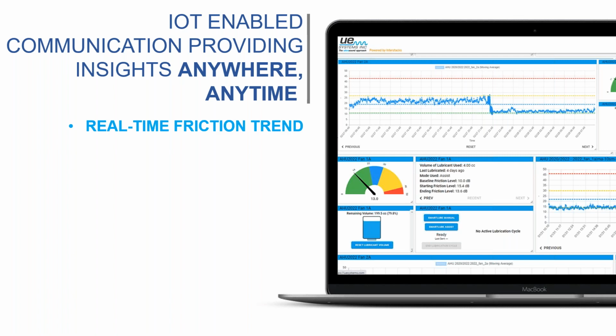So we have a real-time friction trend. Hopefully you can see my mouse. If you can't, that blue squiggly line is that friction trend in this bearing. And you'll notice four dotted lines. That green line is the baseline. That's the ideal. If you look at that Stribeck curve, that's the ideal spot on that Stribeck curve where we're balancing that friction between the amount of grease in that bearing.